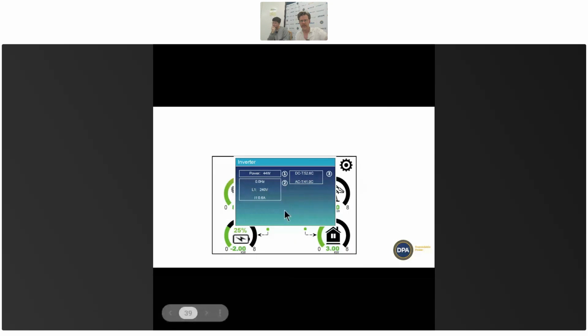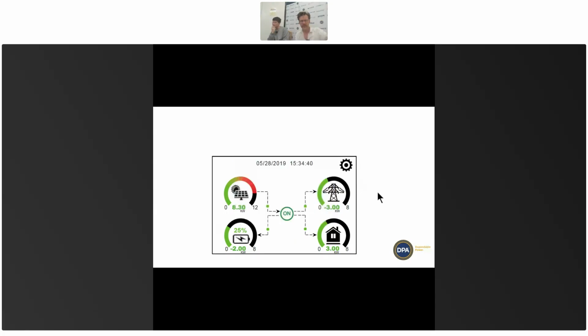And then if you click in the middle, you'll see this general inverter information here. The other thing, just to mention, that's come up a couple of times, is in the middle here, it says on. And there's a switch to the left-hand side of the inverter next to the PV isolation dial. And you need to have it on for it to work. And that's actually quite easy to miss, because the screen will be available even when it's off. So it's just an easy one to get wrong.